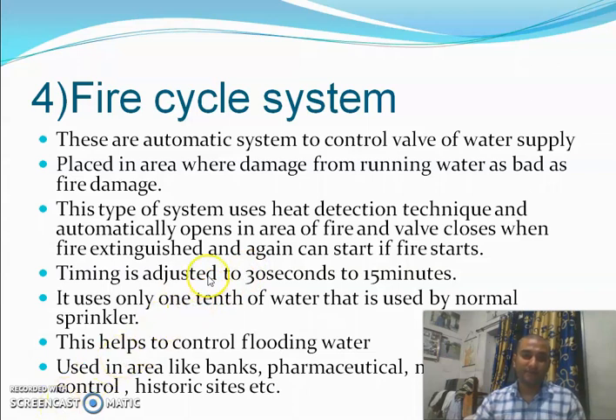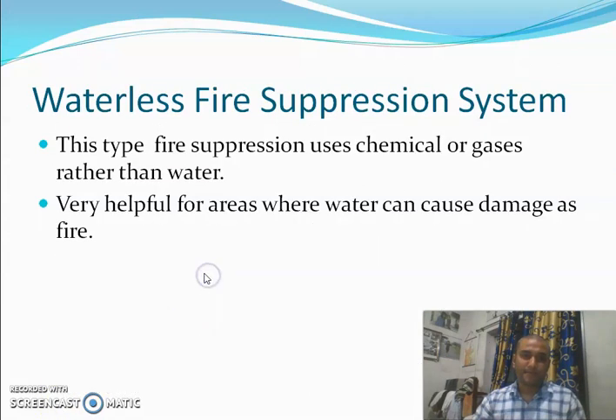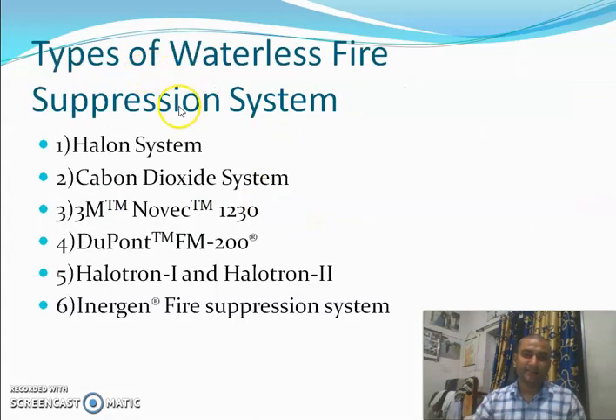Now, moving towards the next topic: waterless fire suppression system. Waterless means without the use of water, that is, the use of chemicals or air or gases to control fire. These are generally of 6 types: Halon system, Carbon Dioxide system, 3M Novec 1230, DuPont FM-200, Halotron 1 and Halotron 2, and Inergen fire protection system.